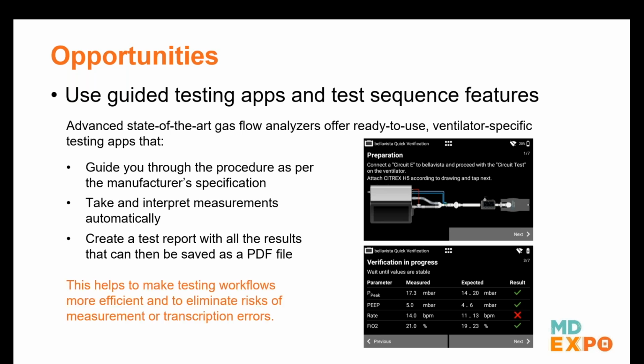So this helps, of course, to make your testing more efficient, and also eliminates the risk of measurement and transcription errors, and also setup errors, because it shows you how to set it up. And additionally, when you start this testing application, it knows what gas standard is being used by this ventilator, it knows the suitable trigger settings, and sets that up for you automatically in the correct manner.